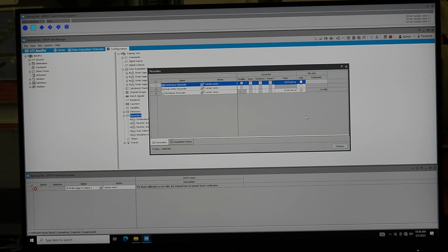And then same thing with the recorder rate, we can set those at whatever maximums for all 8 stations. So you have the 8 different tests assigned to the 8 different stations. You can have a different rate per test up to whatever the max should be. So that should have good full flexibility. I thought it would become limited once you start adding multiple test stations. I don't think so. I think that was the deal, because I think that's a bigger selling point, the 8 independent acquisition rates.